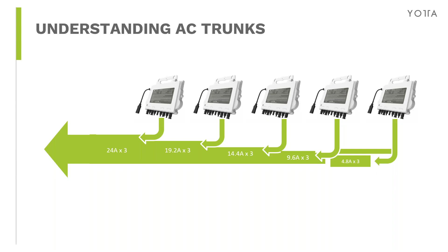As I mentioned before, for people who are not familiar with trunk cables, this is the way it's set up right here, understanding how AC trunk cables work. With a 208-volt version, you're able to put up to 5 inverters or 20 modules onto a single trunk line. So basically you have an AC piece right here that plugs into a single line all the way down here. What we're looking for is how much amperage each one of these devices can put out. As you see, we're putting them in series, so it's 4.8, then it goes up to 9.6, 14.4, 19.2, all the way up to 24 amps, which is the maximum you can put on a 30 amp breaker.